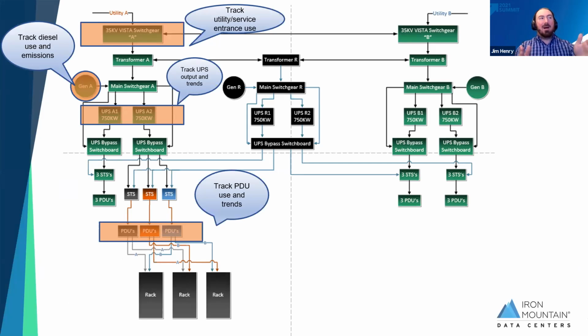Upstream, you've got static transfer switches, then bypasses because you're not always using UPSs, only when you need to go off utility and transfer to backup power. Then UPSs further upstream, main switchgear, and your generators tied into the switchgear so you can go to backup power.